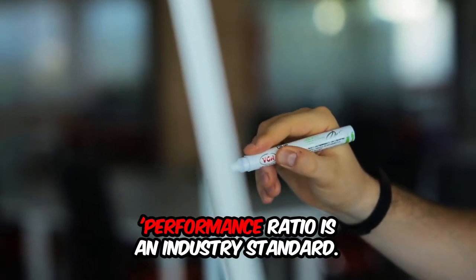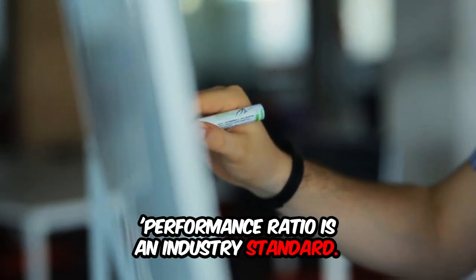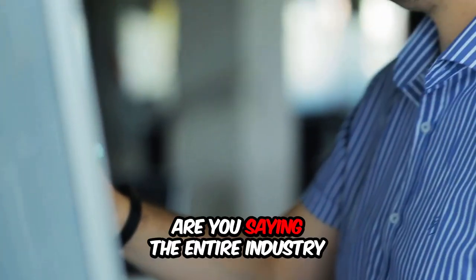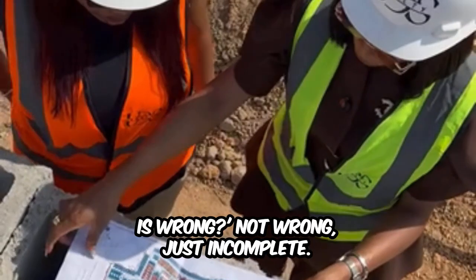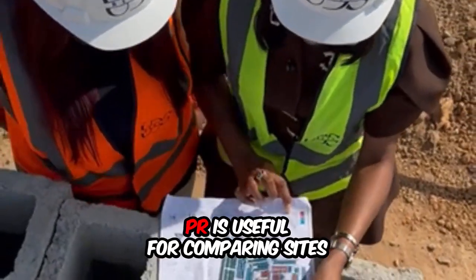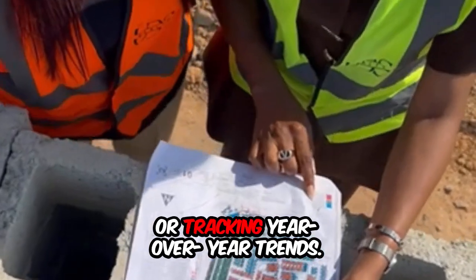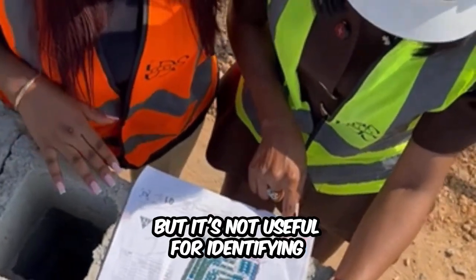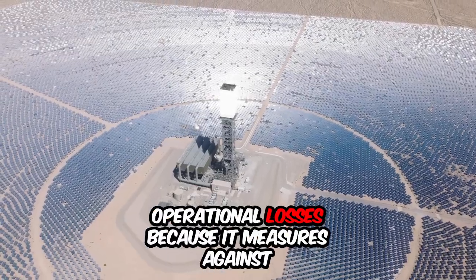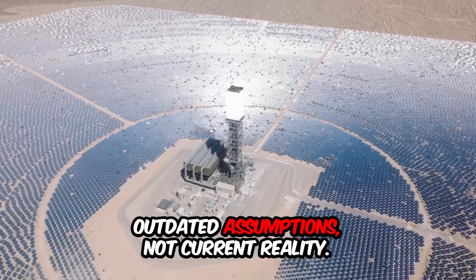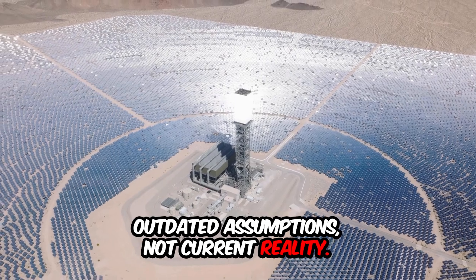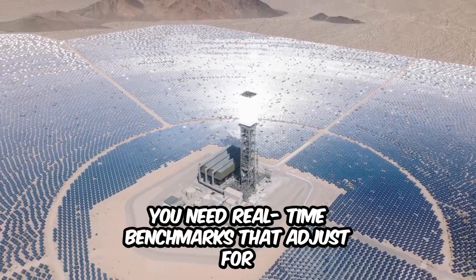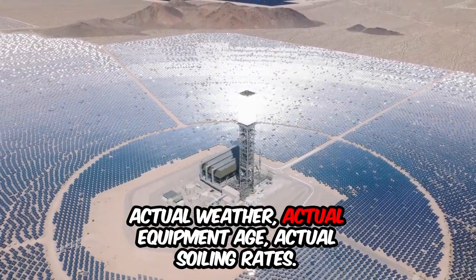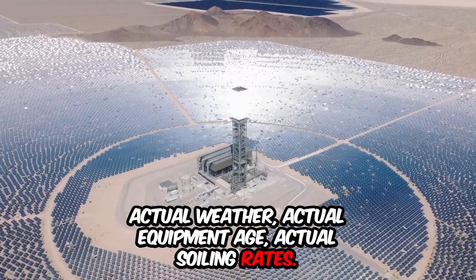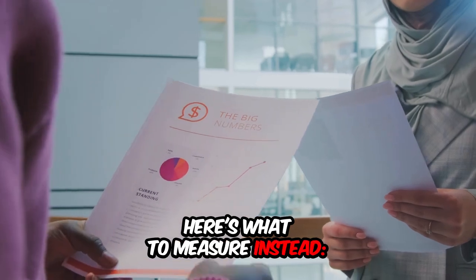You're thinking, performance ratio is an industry standard, everyone uses it. Are you saying the entire industry is wrong? Not wrong, just incomplete. PR is useful for comparing sites or tracking year-over-year trends, but it's not useful for identifying operational losses because it measures against outdated assumptions, not current reality. You need real-time benchmarks that adjust for actual weather, actual equipment age, actual soiling rates. Here's what to measure instead.